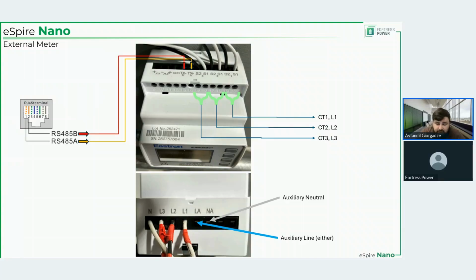One of the ways you could do it, perhaps, would be to use, instead of running two reference cables, so to speak, very small cables, you can run one cable and at the end split it using Wago. And if you have, let's say, a 3-pin Wago, one accepts the output from the reference, and translates into two, one going to line and one going to the line auxiliary. So, for example, instead of connecting the cable from the reference point directly to L1, that L1 would go to Wago, and that would split it to LA and L1. And again, each one could be used. L1, L2, L3 should be fine.